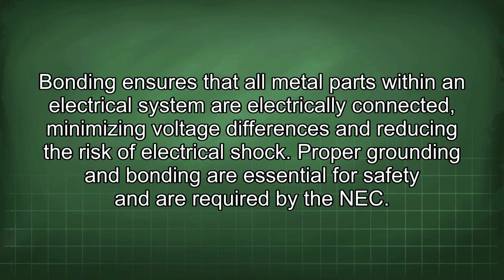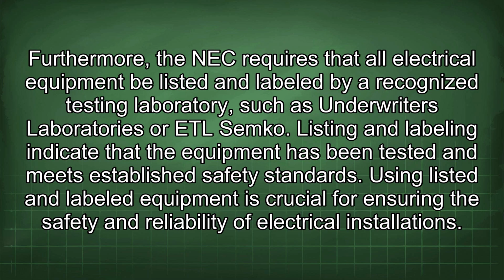Bonding ensures that all metal parts within an electrical system are electrically connected, minimizing voltage differences and reducing the risk of electrical shock. Proper grounding and bonding are essential for safety and are required by the NEC. Furthermore, the NEC requires that all electrical equipment be listed and labeled by a recognized testing laboratory, such as Underwriters Laboratories or ETL Semko. Listing and labeling indicate that the equipment has been tested and meets established safety standards. Using listed and labeled equipment is crucial for ensuring the safety and reliability of electrical installations.